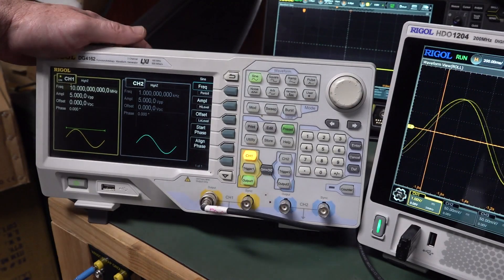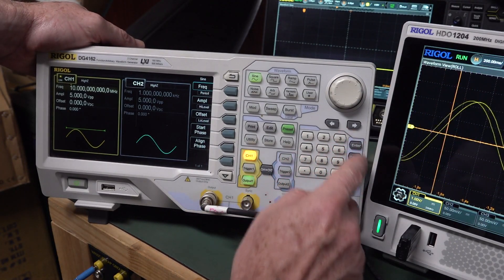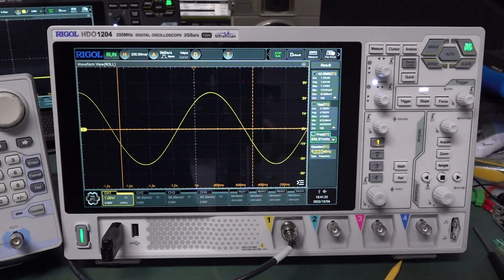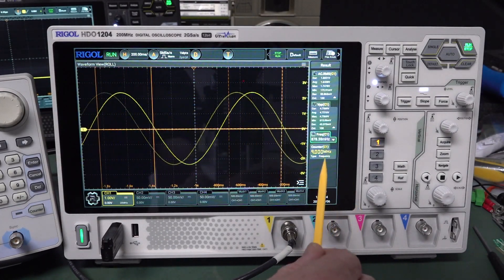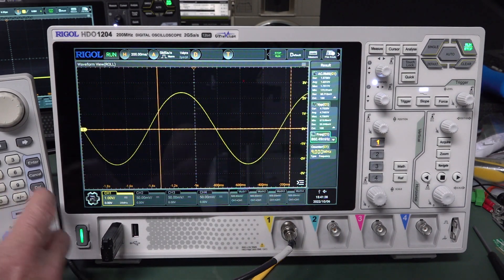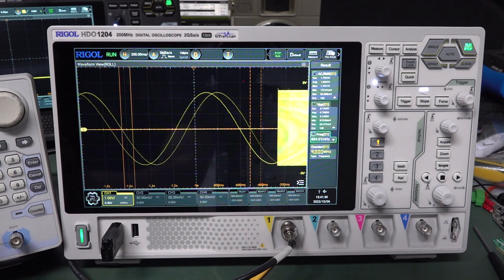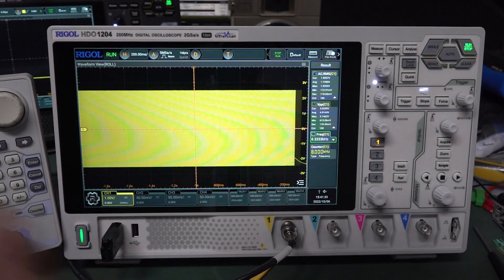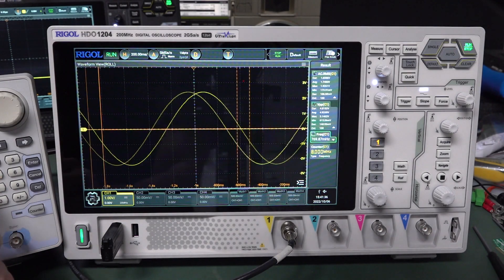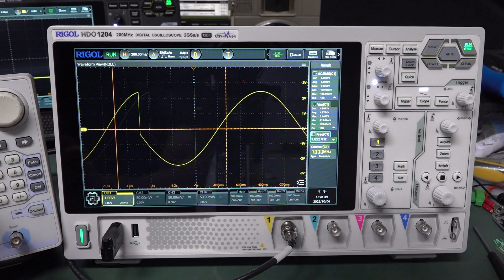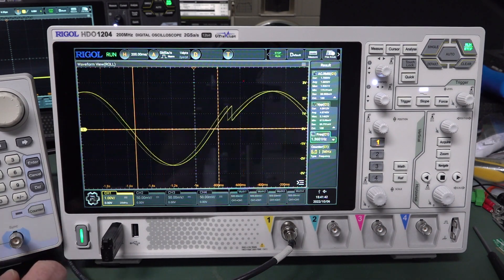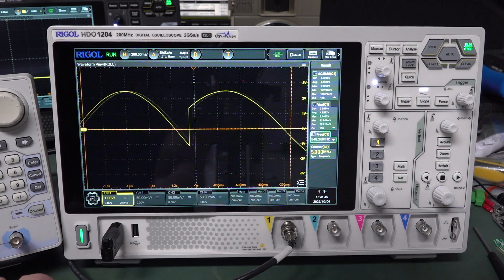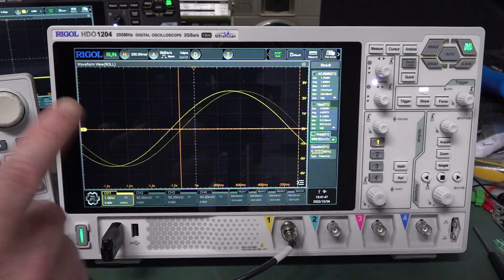Well, let's actually change that, shall we? Let's actually change that over to, let's go 9 megahertz. Okay, so 9 megahertz, it changed there. We've now got 9 megahertz and it's still aliased in there. So let me go down 8 meg, oh, kilohertz, no. 8 megahertz, still there. 7 megahertz, still there. 6 megahertz, and you're getting the idea, right?